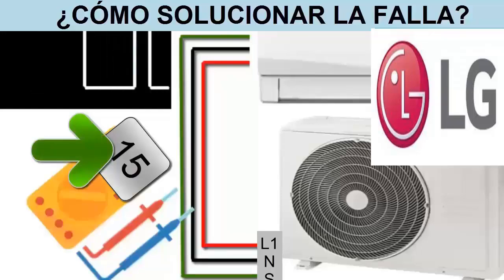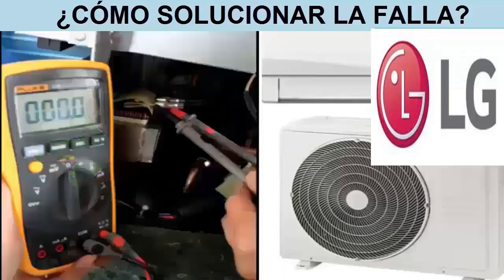8. Before making any replacements, it is recommended to measure the electrical continuity in the reactor located in the outdoor unit using the multimeter on the electrical continuity scale.